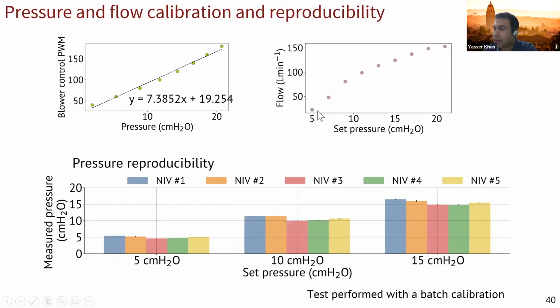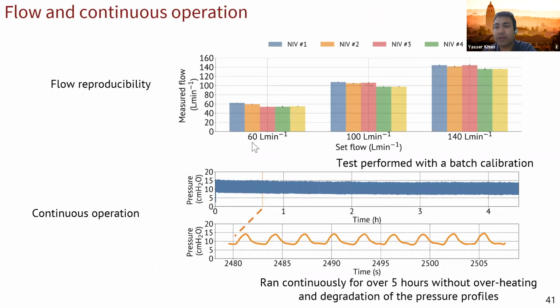And also we can get a good flow. The flow is important because in an enclosed setup where you're wearing the helmet, if you are not maintaining a good flow, there will be CO2 rebreathing. Essentially, when you breathe out, CO2 gets trapped within the helmet, and that's detrimental. Also, we did flow reproducibility testing where we checked for 60, 100, and 140 liters, and ran the devices for a long time. Here, we're showing data for 4 hours, but it can actually go for days.